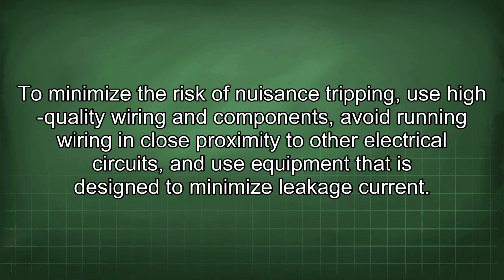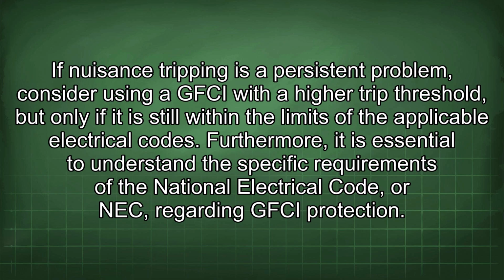To minimize the risk of nuisance tripping, use high-quality wiring and components. Avoid running wiring in close proximity to other electrical circuits, and use equipment that is designed to minimize leakage current. If nuisance tripping is a persistent problem, consider using a GFCI with a higher trip threshold, but only if it is still within the limits of the applicable electrical codes.